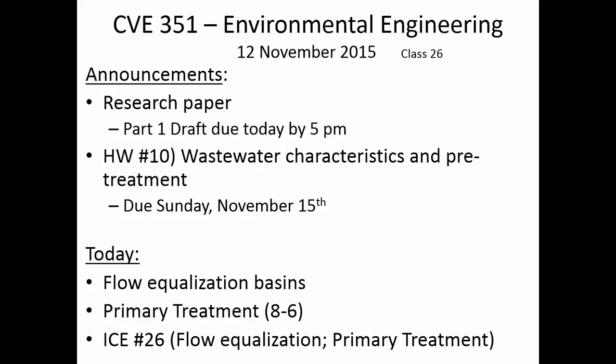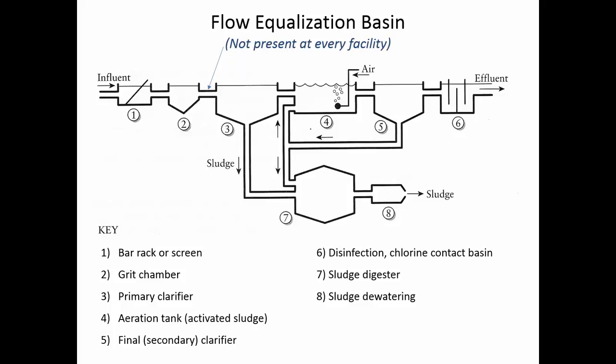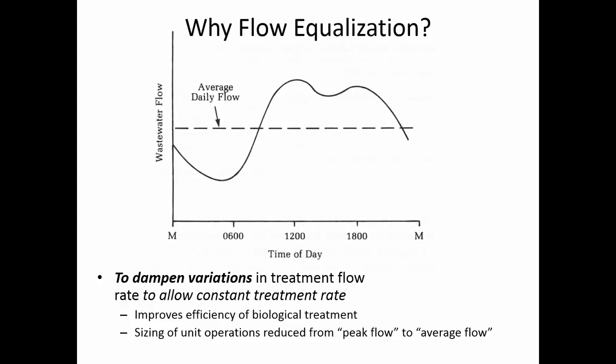After we do flow equalization basins, we're going to talk a little bit about primary treatment. Flow equalization basins aren't at every treatment plant. They're usually put into place when there's a huge variation in the flow rates between the daytime and the nighttime. Flow equalization basins are meant to smooth out the BOD loading and the flow loading because the bacteria are going to require steady state conditions. We want to dampen the variations.